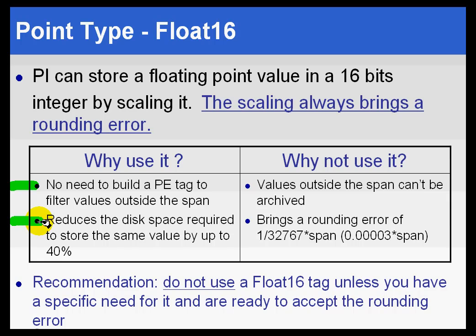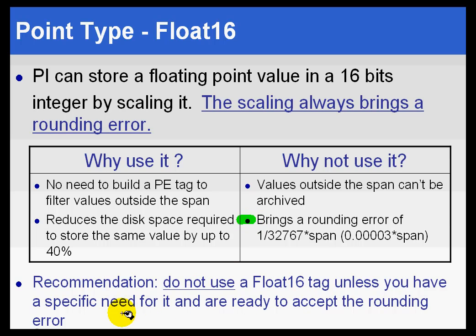Float 16 has built-in clamping on the zero and span of a tag so that values cannot go below zero or above zero plus the span — Float 16 will do that automatically. You wouldn't have to build a separate PE tag to make that clamping. It also reduces disk space required. However, the same thing you might call a feature is also a liability: it cannot archive anything beyond the span. So if you have a level that goes from zero to 100%, it may sometimes go up to 101% due to calibration problems, but this will stay clamped at 100%. It also introduces a rounding error. Unless you have a specific need, we suggest you avoid the Float 16s.